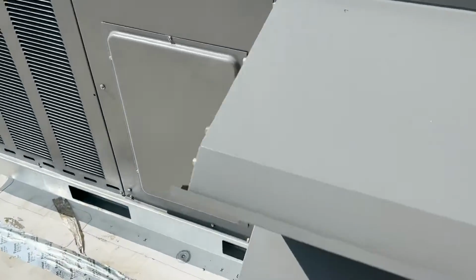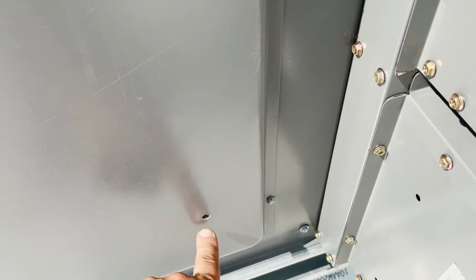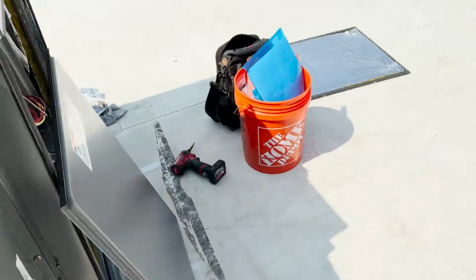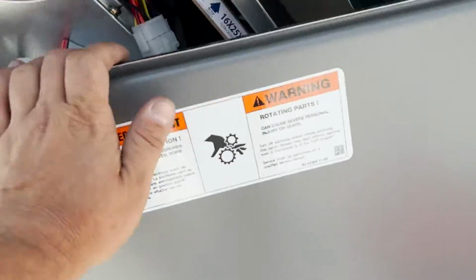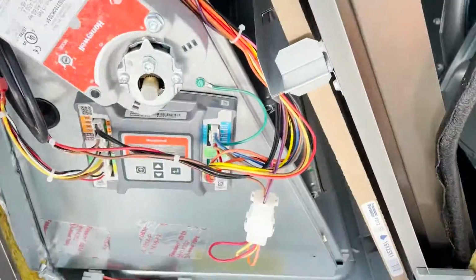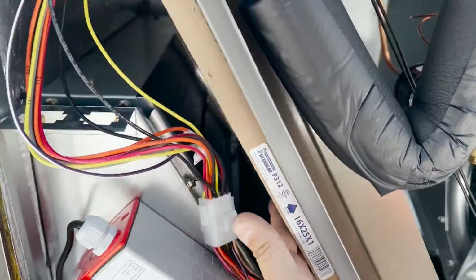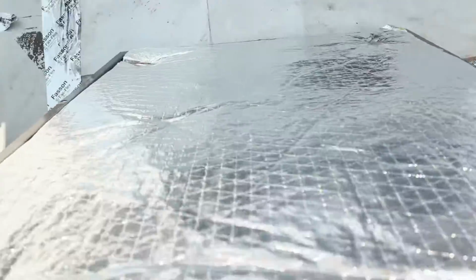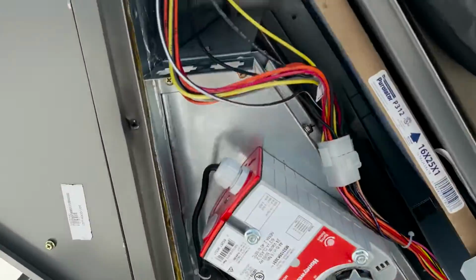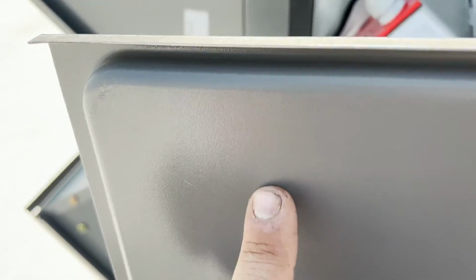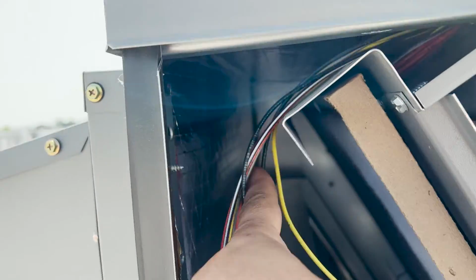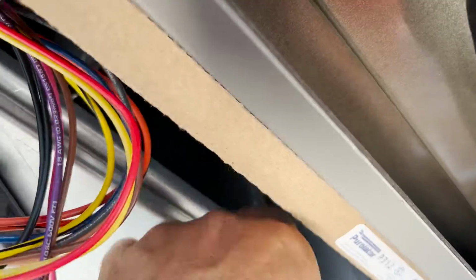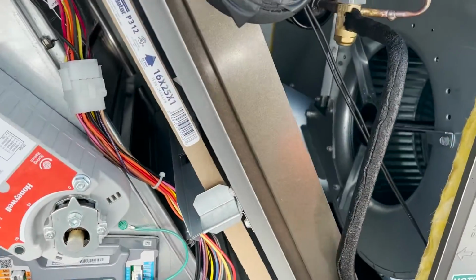All right, test ports. I like to put one here in our supply side. Return side's rough because static pressure doesn't really matter, but temp split it does. We want to be before our filtration. You can kind of see it on the line here. So we can either be up in this corner, which works great for static pressure, but not very accurate for a temp split. To get a temp split, you really want to be in front of this grill for a return or use a wireless probe.